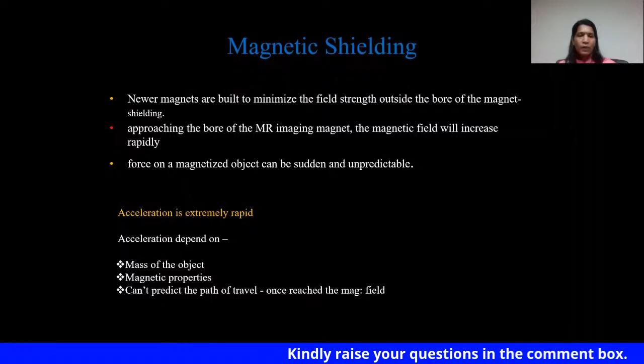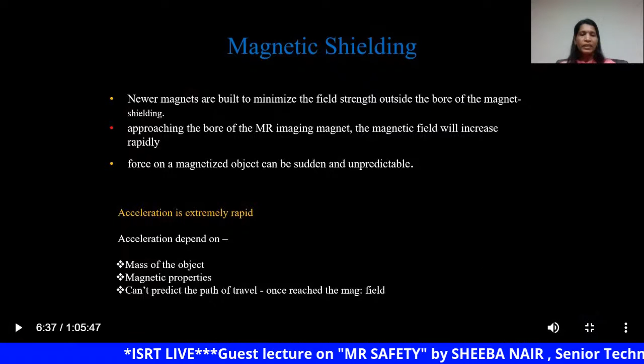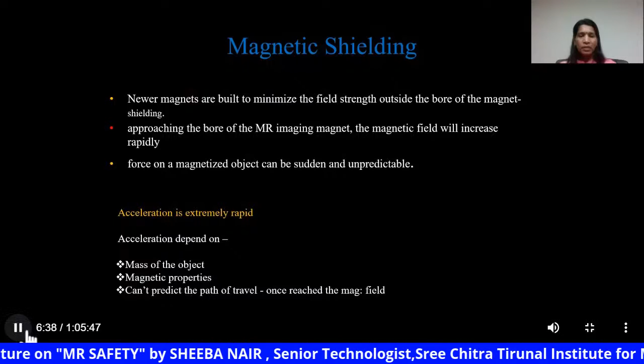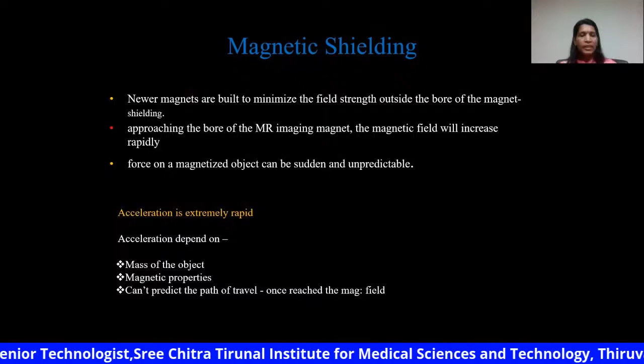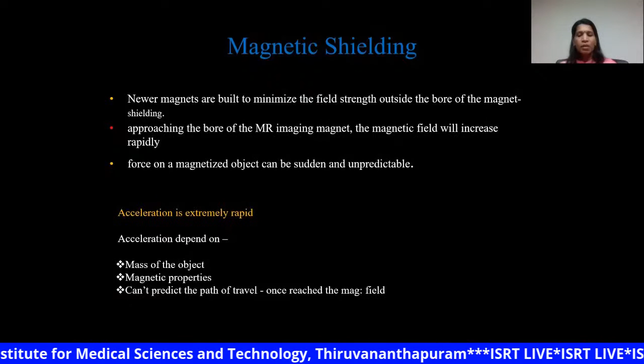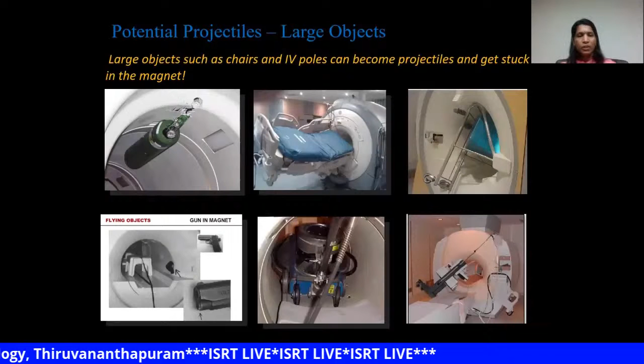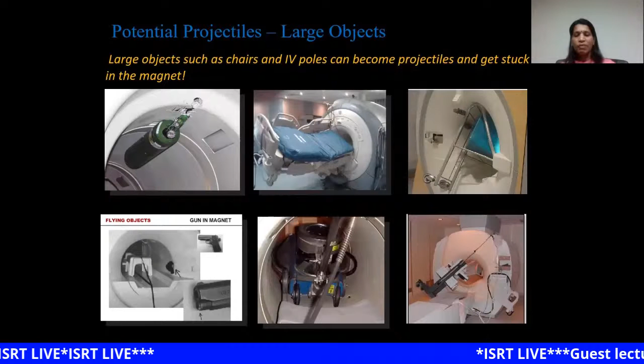So in a shielded system, until we approach the bore, the attractive forces will be less. But once we approach it, the magnetic field will start to pull the device with a huge force. This effect will be sudden and unpredictable, and the acceleration of a device depends upon the mass of the object and the magnetic properties of the object. If the mass is high, then the acceleration will be more. If it is a ferromagnetic material, then the acceleration will be more. Even if we think a larger object will not be pulled into the magnet, that is false. These are potential projectiles that have occurred in several places.